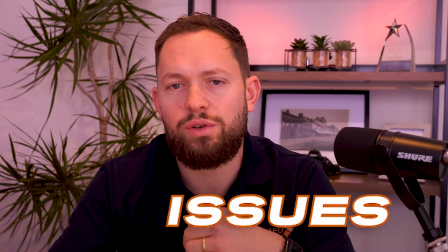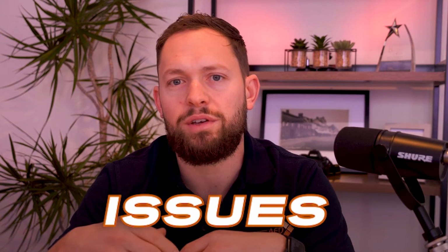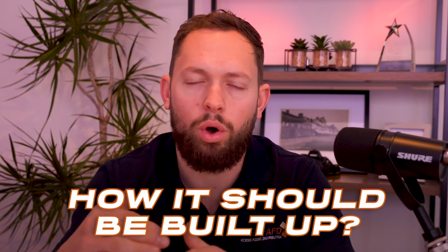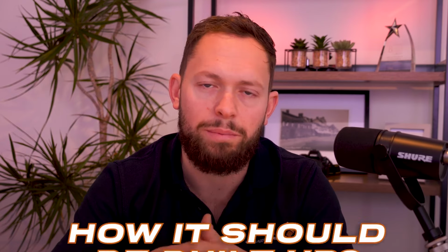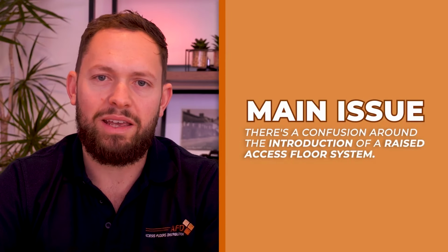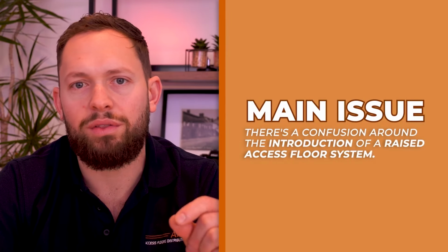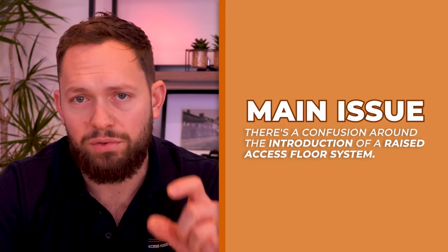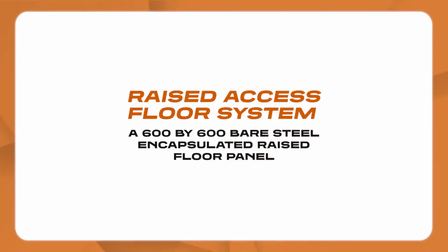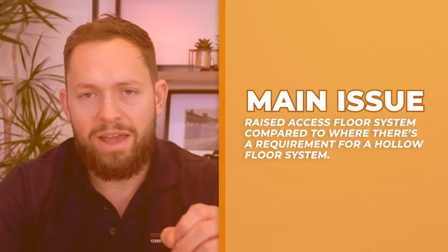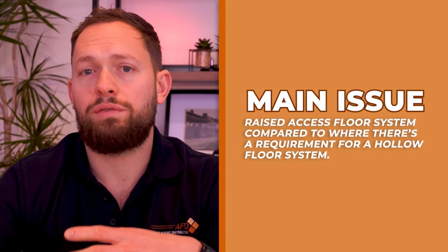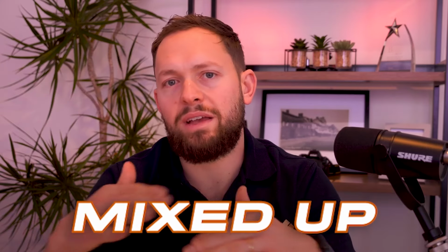And today in this video we're going to talk about some of the issues that we identify in terms of how a raised floor or hollow floor system should be built up and the components that should form part of it. Quite often the main issue I see is where there's confusion around the introduction of a raised access floor system. When I talk about a raised access floor system, I'm talking about a 600 by 600 bare steel encapsulated raised floor panel, compared to where there's a requirement for a hollow floor system. And quite often the two get mixed up.